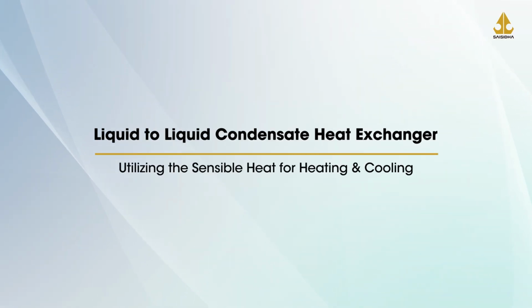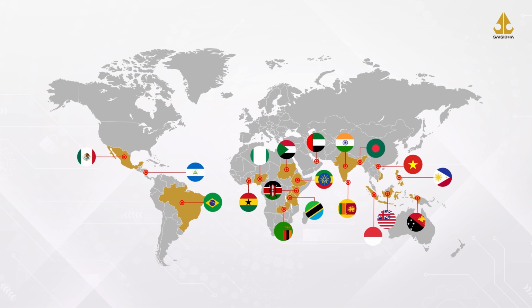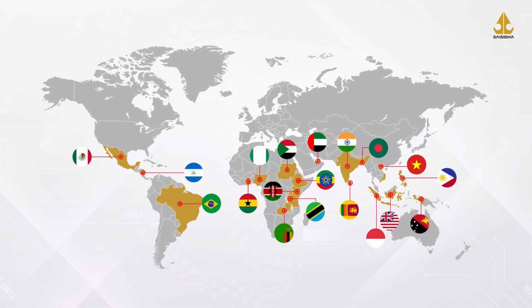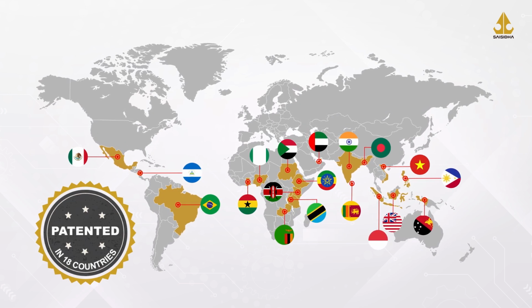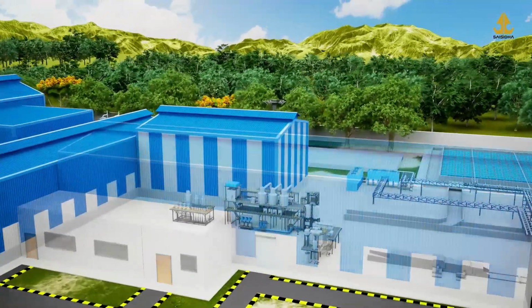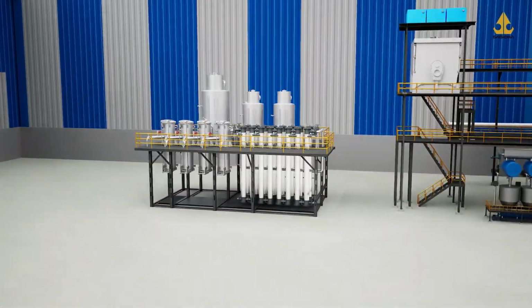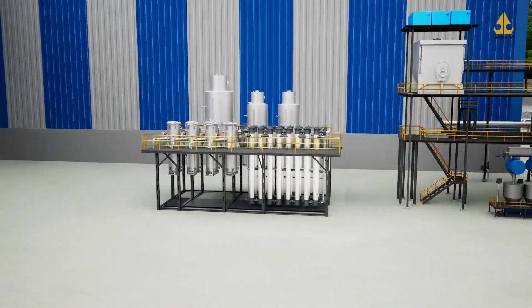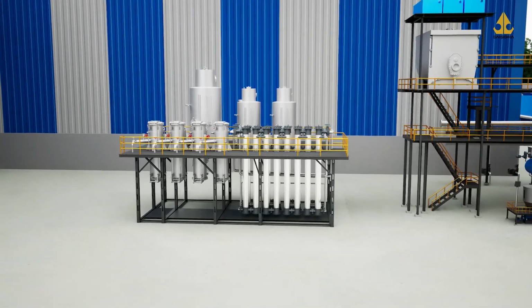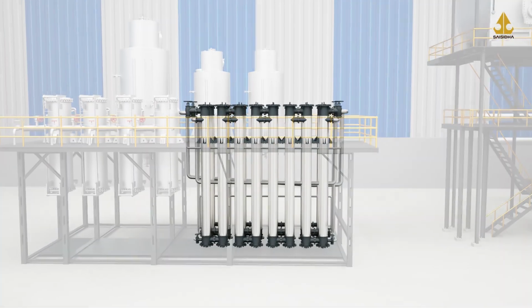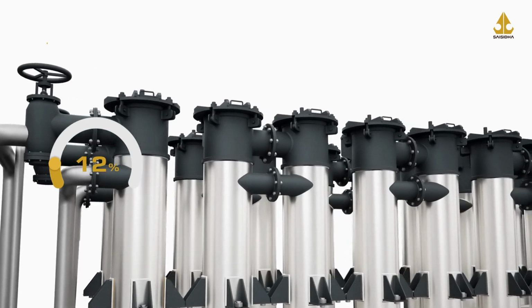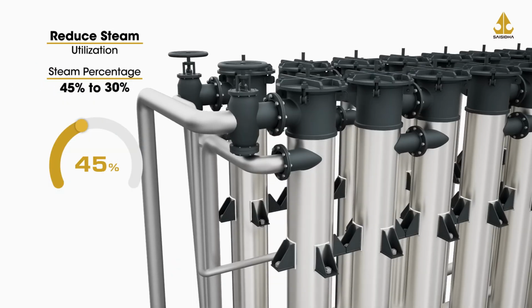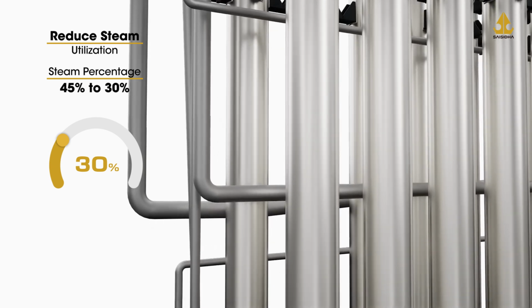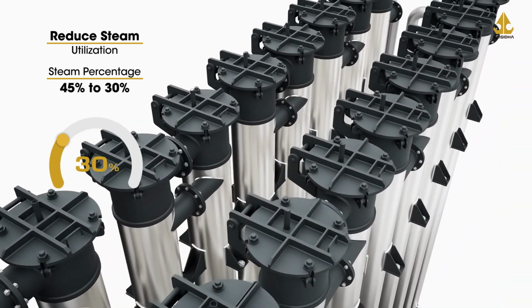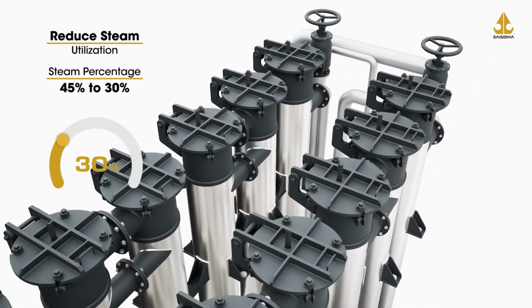We introduce our innovative liquid-to-liquid condensate heat exchanger, utilizing the sensible heat for heating and cooling applications, patented in 18 countries. A groundbreaking solution for sustainable and efficient sugar processing. By installing the patented system in conventional existing plants, we have helped reduce steam percentage on cane from 45% to 30%, on cane for power production, with some minor modifications to the plant.